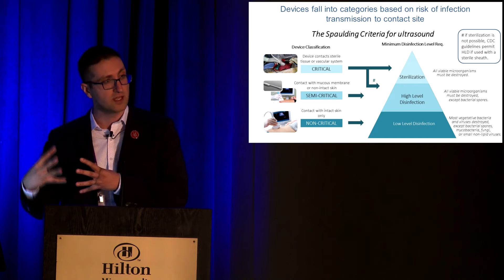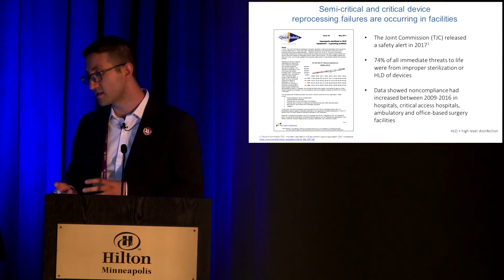Okay, so it's a combo in lieu of sterilization. In addition to all that, Joint Commission released a safety alert in 2017, basically detailing how poorly we are doing at managing ultrasound probes and actually disinfecting them appropriately. 74% of all immediate threats to life were from improper sterilization or high-level disinfection of these particular devices, and data showed non-compliance increased from 2009 to 2016.